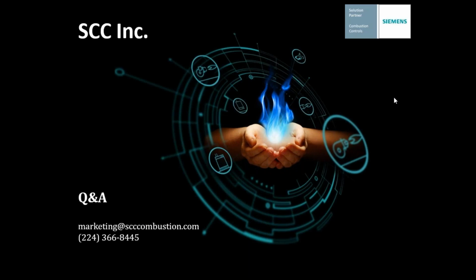So the first question is, are all the common terminals connected internally, or do they have to be jumpered? And the answer would be no, they're all internally connected. So when you do connect to one protective earth, all the protective earth terminals inside the LMV are connected internally. And so you only have to provide one connection there from the line voltage coming in with the protective earth, and then anything you connect to any one of the protective earth terminals would be common.